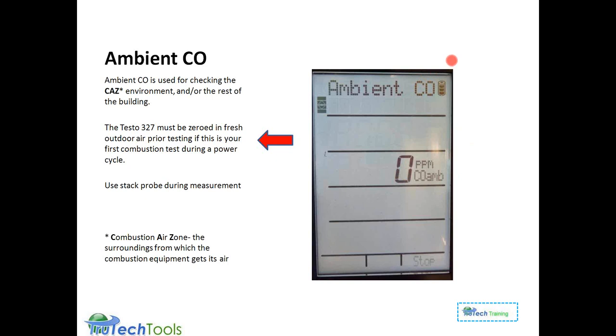The ambient CO test is used to measure basically CO in the breathing air. Again, the 327 needs to be zeroed in fresh air if this is the first combustion test during a power cycle. And a power cycle is power on, power off. In between the two is the power cycle. In other words, things reset in that power cycle. So if you've been running it doing another type of test and you've already zeroed it and you move on to an ambient CO test, it won't ask you again to do the zeroing. But it will happen if it's the first test you do during a power cycle.